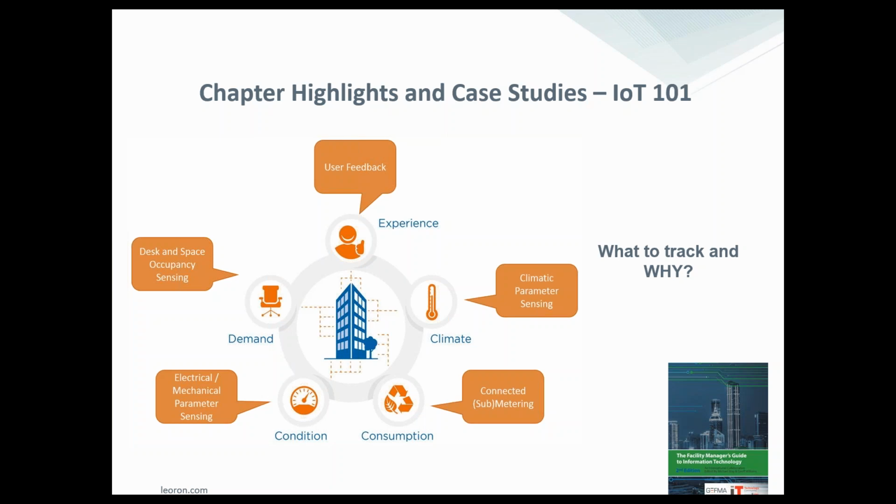But if you looked at that trend over a 30-day period, what you could see is that gradual incremental change in vibration, which means that we're starting to get to a failure state. And we can change out equipment, we can repair equipment, we can do all of those things in a planned way, and with no downtime, or at least a planned downtime for our occupancy.